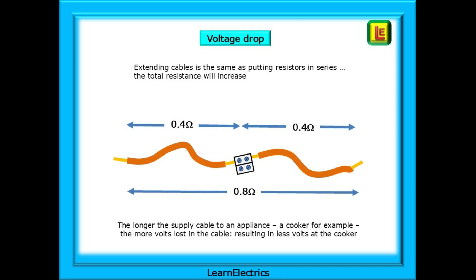Extending cables is the same as putting resistors in series. The total resistance will increase. Copper cable will have its own very small resistance. And here, we've joined two 0.4 cables together, with the result that the overall cable resistance is now 0.8 ohms. The longer the supply cable to an appliance, a cooker for example, the more volts lost in the cable, resulting in less volts at the cooker. Less volts at the cooker means it takes longer to boil a pan of water. Perhaps only seconds, but somebody has to pay for that extra electric.